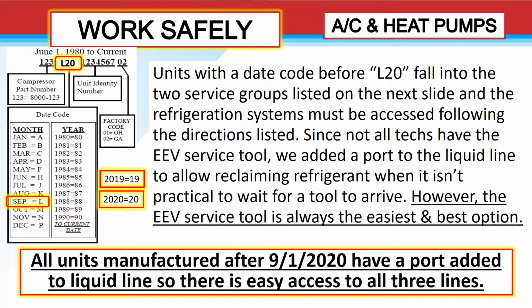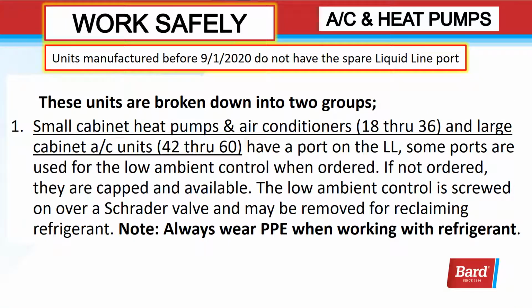Since not all techs have the EEV service tool, we added a port to the liquid line to allow reclaiming refrigerant when it isn't practical to wait for a tool to arrive. However, the electronic expansion valve magnetic service tool is always the easiest and best option. These units are broken down into two groups. First group is small cabinet heat pumps and small cabinet air conditioners and large cabinet air conditioners.